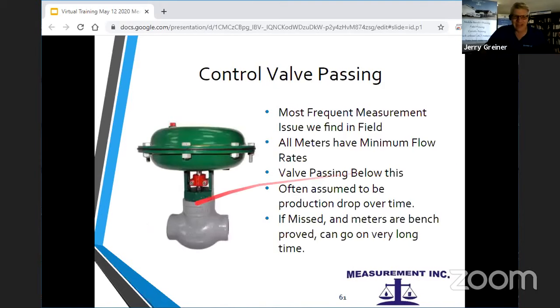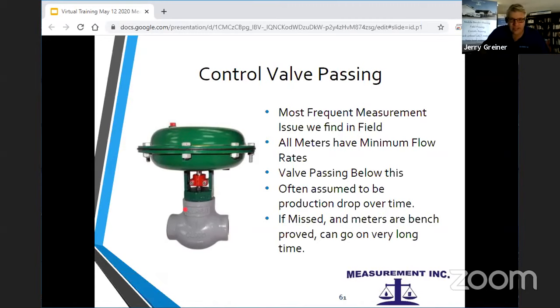Okay, control valve passing. We're going to talk about control valves here because really it's the most frequent issue we find. If we go out in the field, somewhere around 1 in 10 we find passing when you check them. Every meter has a minimum flow rate, which we've sort of talked about already, and passing valves are normally way below the minimum flow rate. And when they pass, it's often assumed to be production dropping over time. If it gets missed, they can go a long time, and there's quite a few of these that are on fairly low wells, like the ones we've seen lately.